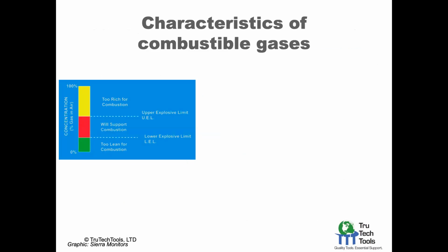So getting right into it, a combustible gas itself, just the gas itself, responds differently depending on the concentration of air and gas. Will it support combustion? Does it have too much gas, in other words too much fuel, and too little air to actually combust or burn? It's in the combustible range here, the red range, the middle bar. The bottom range, the green, is too lean to support combustion. And so this is the concentration of gas compared to the air. So you go from 0 combustible gas all the way to 100% combustible gas. I think everybody can imagine that at 100%, there's just no oxygen around, because you need oxygen in order to combust. I think you probably all know that from your combustion training classes.